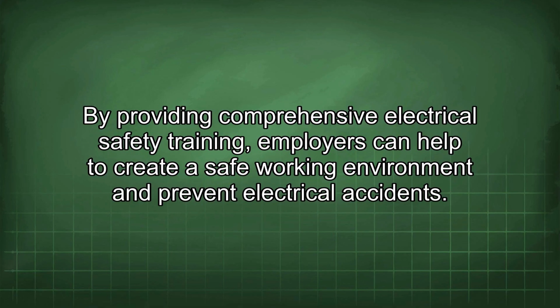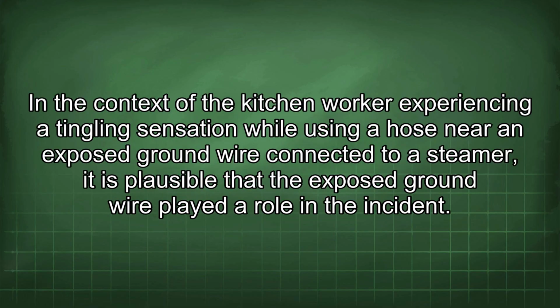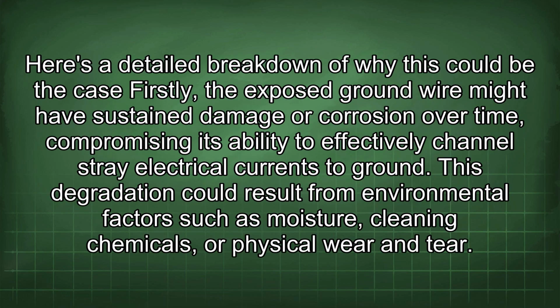In the context of the kitchen worker experiencing a tingling sensation while using a hose near an exposed ground wire connected to a steamer, it is plausible that the exposed ground wire played a role in the incident. Here's a detailed breakdown of why this could be the case. Firstly, the exposed ground wire might have sustained damage or corrosion over time, compromising its ability to effectively channel stray electrical currents to ground. This degradation could result from environmental factors such as moisture, cleaning chemicals, or physical wear and tear.